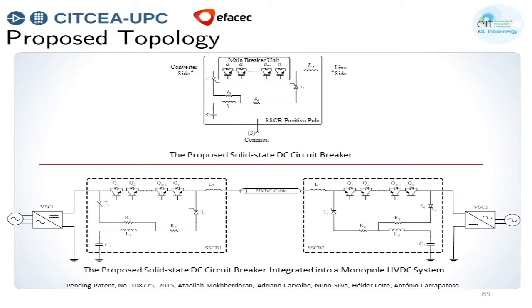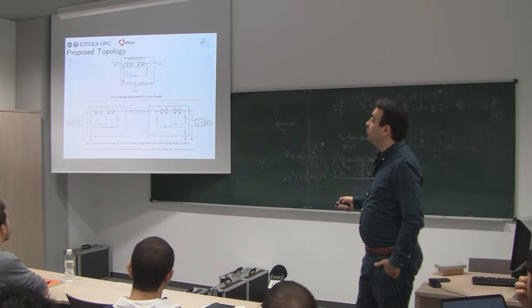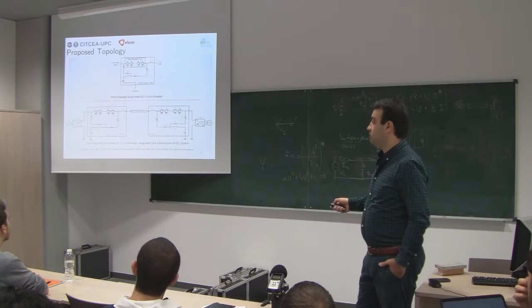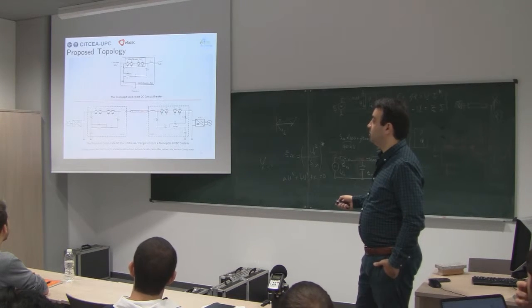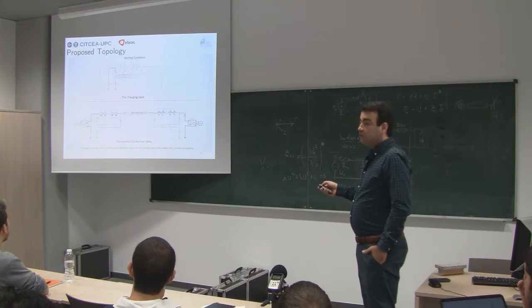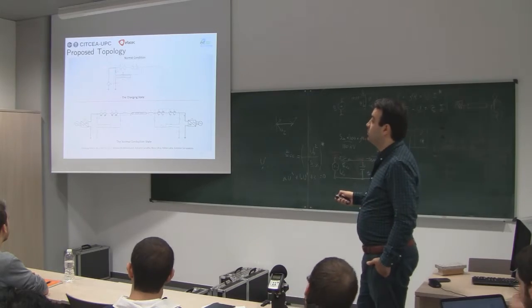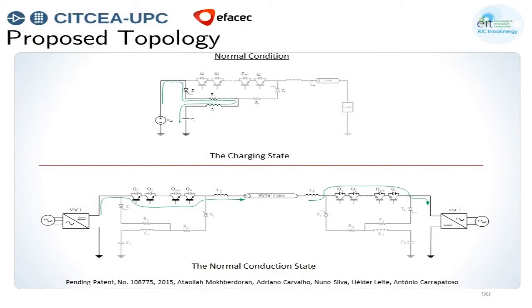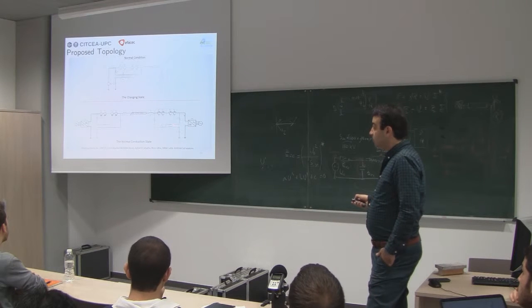So if I want to show you how we integrate this topology into an asymmetric monopole HVDC configuration, it will look like this. You will have the converter here, you will have a breaker here, you will have the cable here, and you will have a breaker here which looks to the opposite side. All the emitters of these IGBTs are looking to the cable, and all the emitters of these IGBTs are looking to the cable. So the operation principle: we are charging this capacitor through this branch by triggering this thyristor. After having it charged up, we are closing the breaker main branch, and we have the current flowing, if this converter is supposed to be the rectifier, through the IGBTs and the cable and through the anti-parallel diodes here to the other converter.